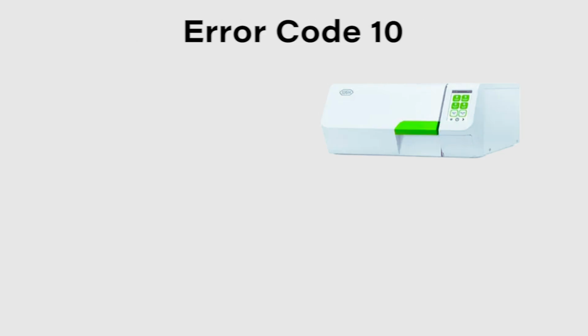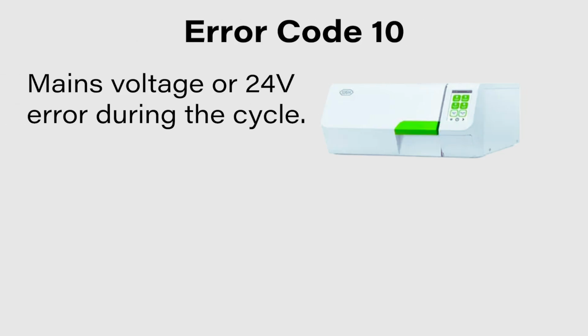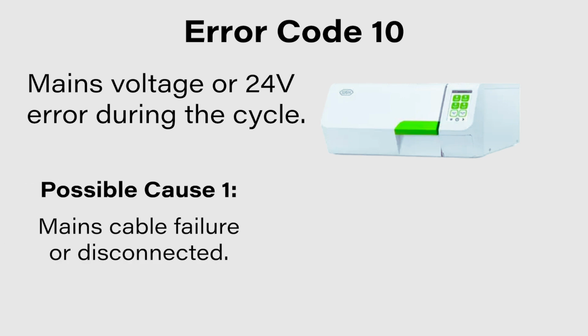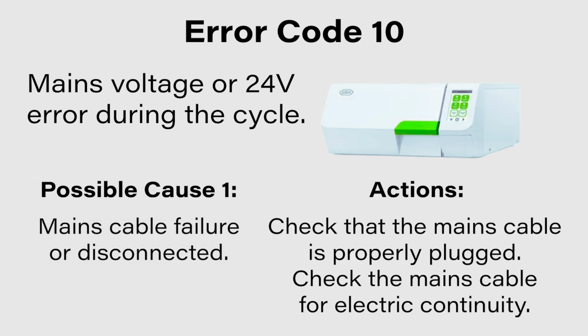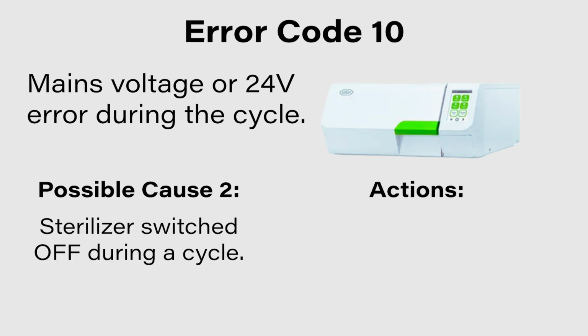If your W&H Lexa Mini Autoclave displays an error code 10, there was a mains voltage or 24-volt error during the cycle. The first possible cause is that there was a mains cable failure or it was disconnected. For this, check that the mains cable is properly plugged and check the mains cable for electrical continuity. The second possible cause is that the sterilizer was switched off during a cycle.